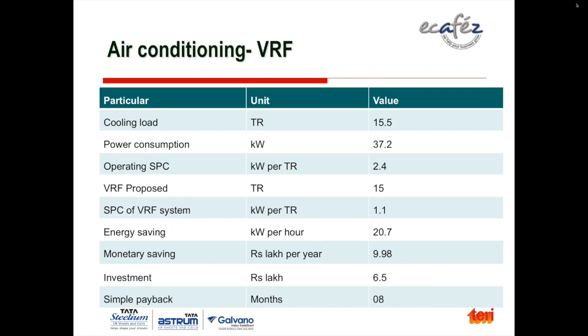As you can see, it's a huge amount of saving. Essentially, one can get 1.1 with the best VRV system available with Daikin. Some of the other manufacturers normally have slightly higher, 1.4 or 1.5 kilowatt hour consumption per TR. Energy saving per hour is 20.7 units. Monetary saving per year is almost 10 lakhs. Investment in the new VRV system was 6.5 lakhs, which pays back within just 8 months.